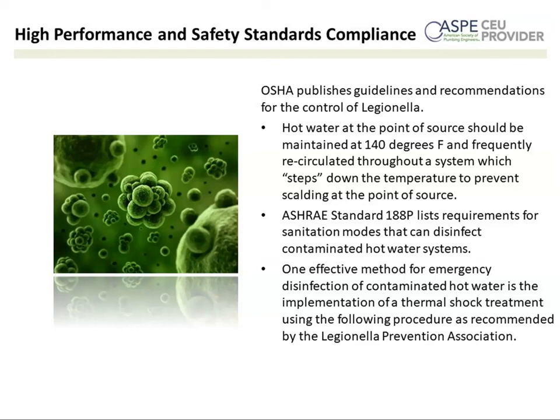And we at Watts look at Legionella as a multidiscipline approach, right? There are different ways to attack it. And if you look at a lot of the cases that are in the news, you'll see that a lot of the remediation involves numerous types of disciplines to address the Legionella. In some cases, you might see a hot water flush, you might see filtration, you might see chlorination and filtration, you might see copper silver ionization. So having a multidisciplined approach, depending on the situation, and every situation is different, is really important.